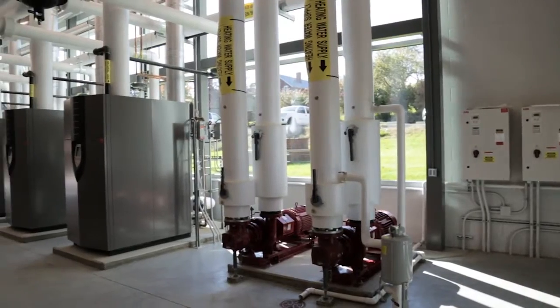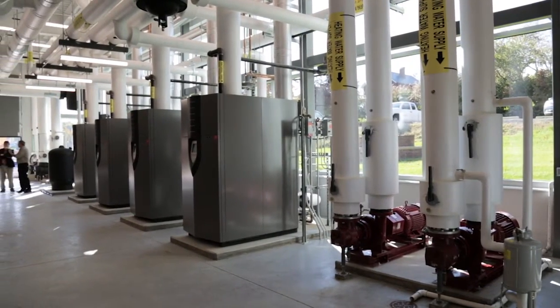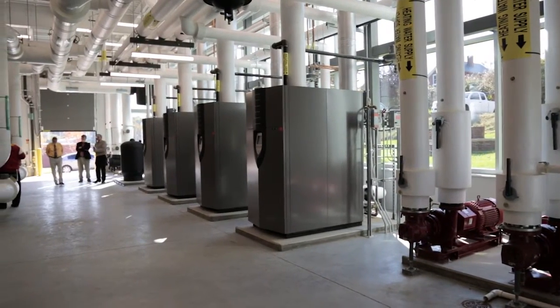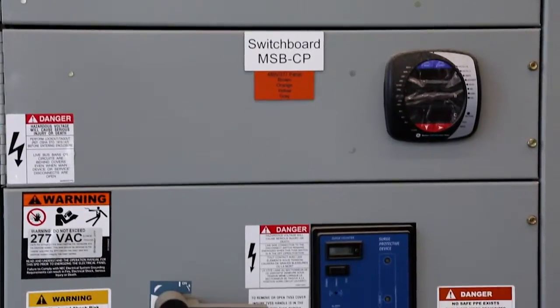We've estimated that we've saved at least 3,000 square feet total in those three buildings by having the central plant located here to serve them. So that space was captured more for teaching in those buildings, and then you've got teaching in this building too. Simultaneously, the maintenance factor is greatly reduced because you can do all of your maintenance on this equipment with probably one guy in one space, and you don't have to have someone traveling between the buildings to monitor all of this equipment. All of the connections that were saved, there's no doubt about it.